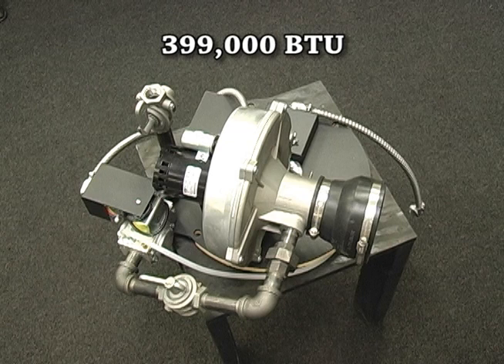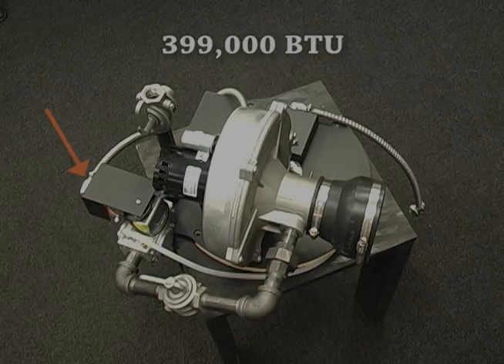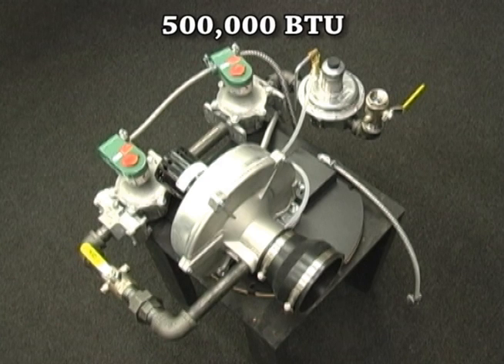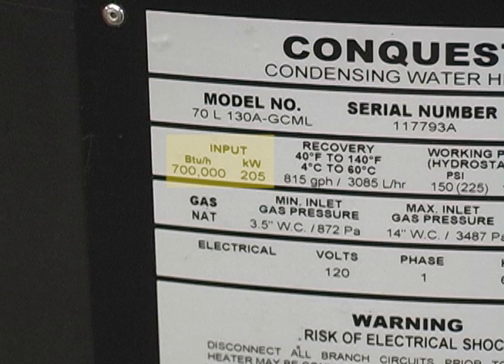The 399,000 BTU input units have an on-off control system with a combination regulator and gas valve. Heaters with inputs of 500,000 BTU and above use a modulating control system with a larger regulator and separate gas safety shutoff valves. We will address both burner systems separately. Identify your burner control system prior to making any adjustments.